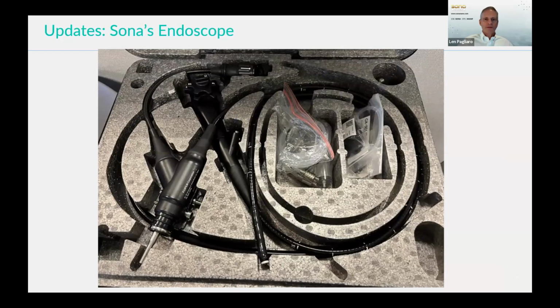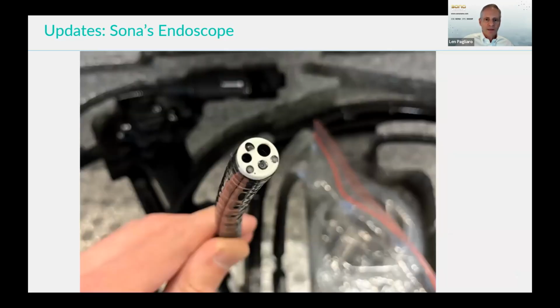Here's the endoscope we had delivered recently from Fuji. We started a collaboration with Fuji to develop this system, and they've been very supportive. Here's a picture of the business end of the endoscope. There are two darker holes, the working channels in the scope—one about 2+ millimeters in diameter, the other 3+ millimeters—plenty big enough to put fibers through. We've already got our fiber running through that channel delivering infrared light. It's going to be a really nice system, and again, this is an off-the-shelf endoscope.